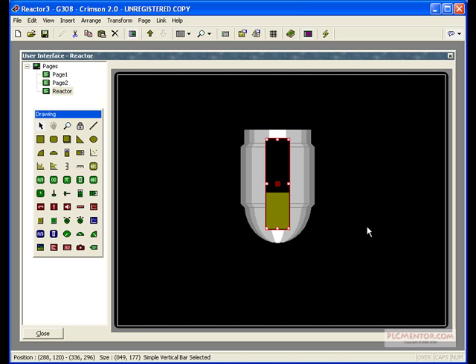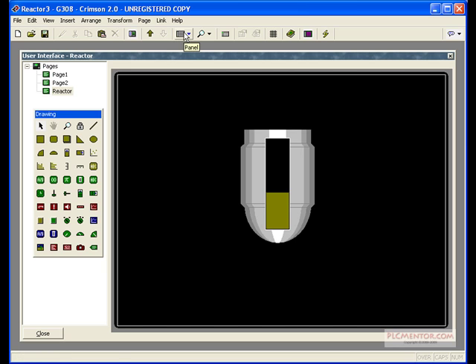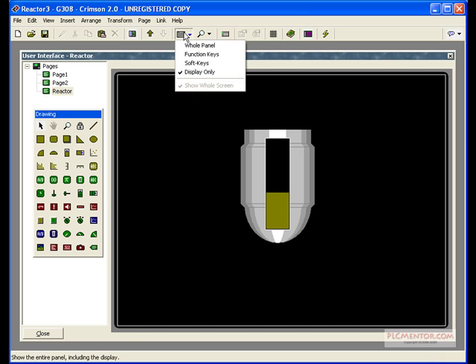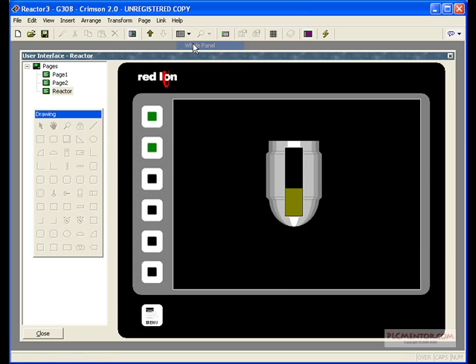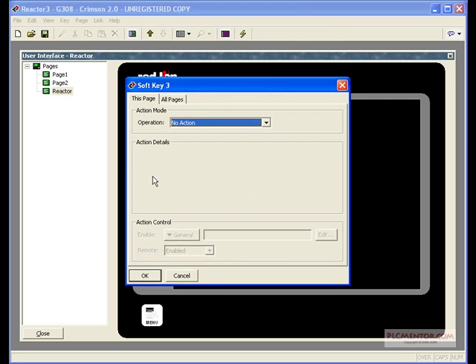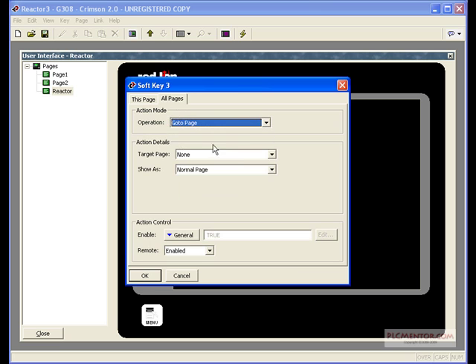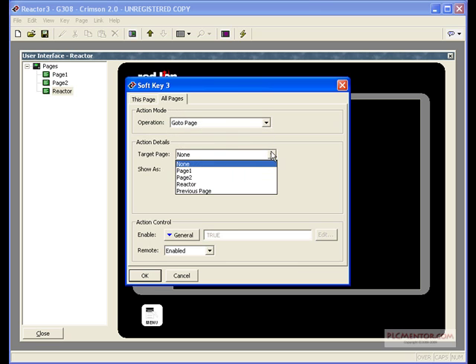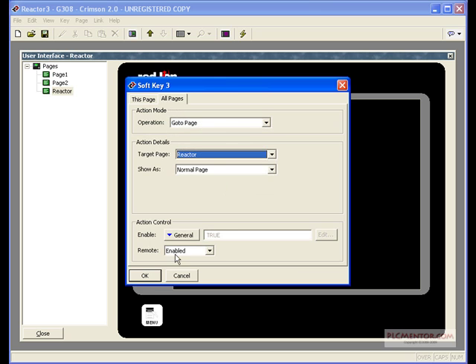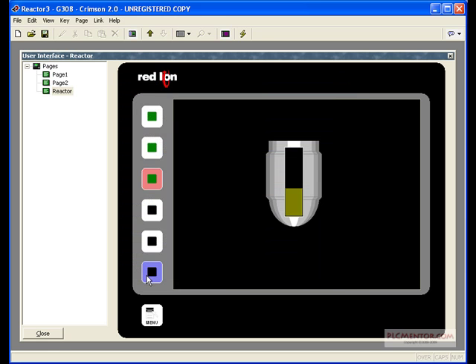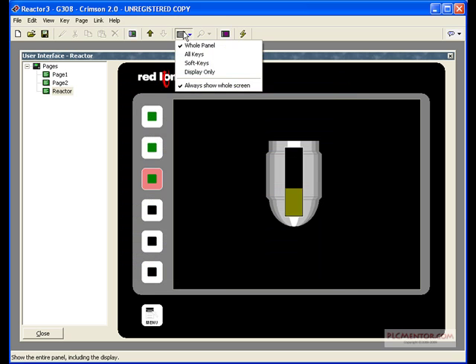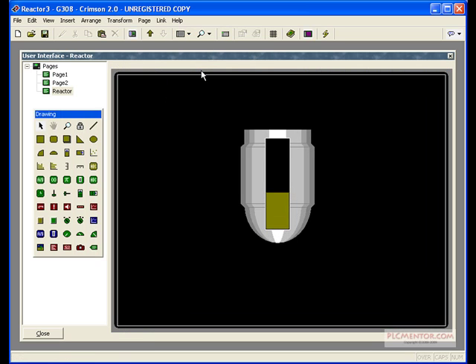And now, we still need a way to navigate to this new screen we've created. Let's go up to our Page Menu panel. Select Whole Panel, and we'll select our third Function button. We'll assign Softkey 3 all pages to GoToPage Reactor. OK. We'll go back in our Panel Menu and go to Display Only.